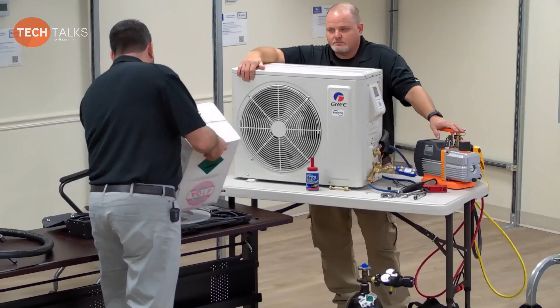So, excellent. We already talked about adding additional charge and piping rules and things like that. If you're needing to add charge for your additional line length, we've got a scale over here that Greg was kind enough to bring as an example, and we've got our refrigerant tank. We want to make sure that we're taking that refrigerant tank and we're turning it upside down, right?